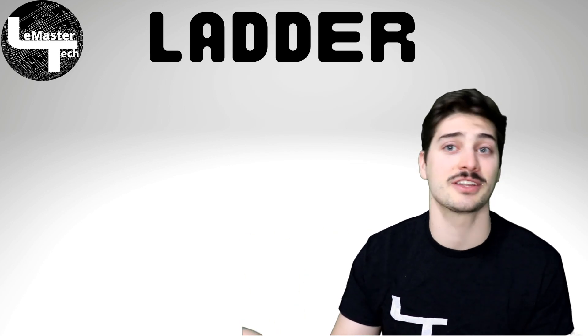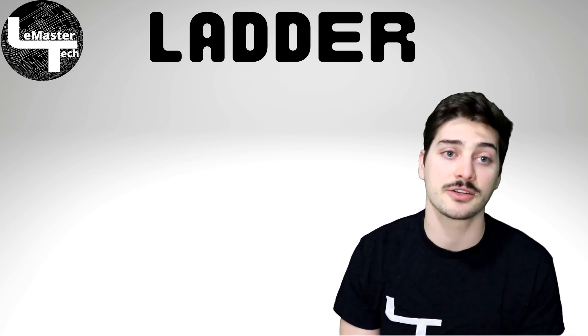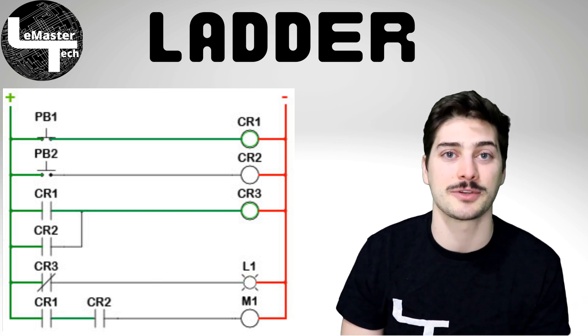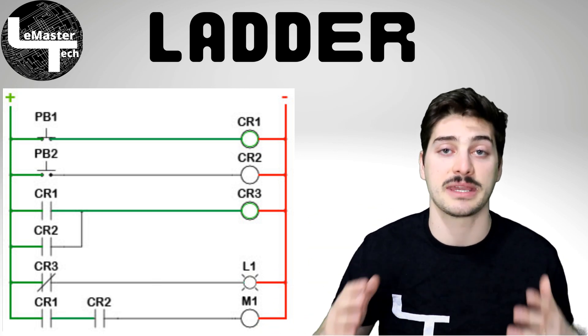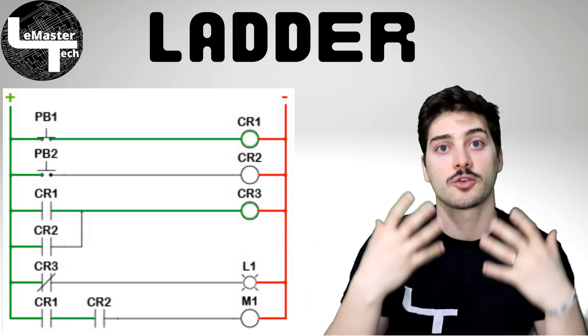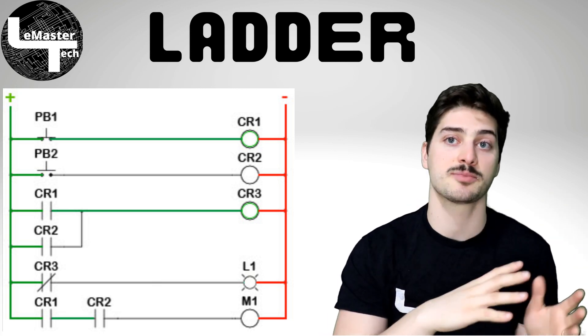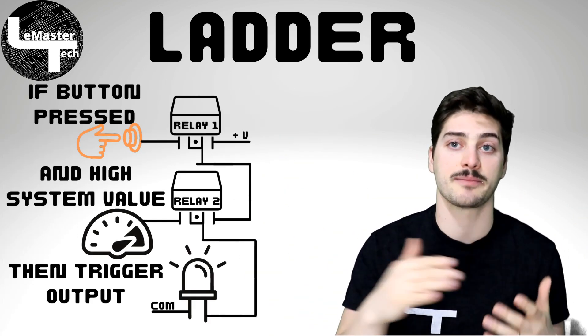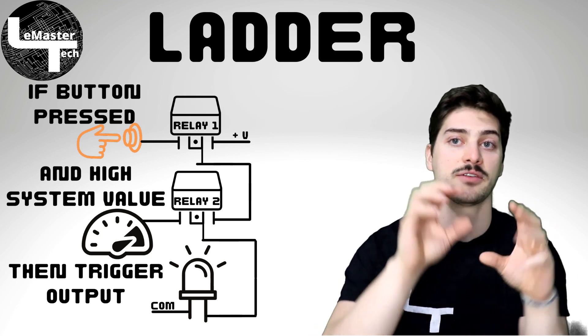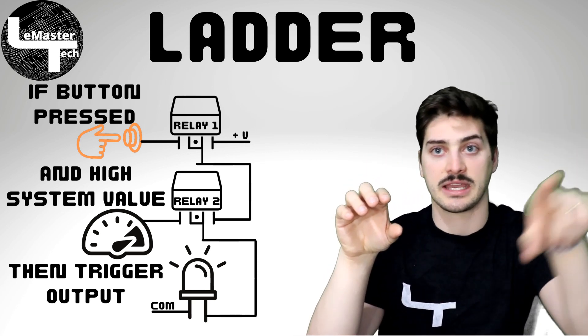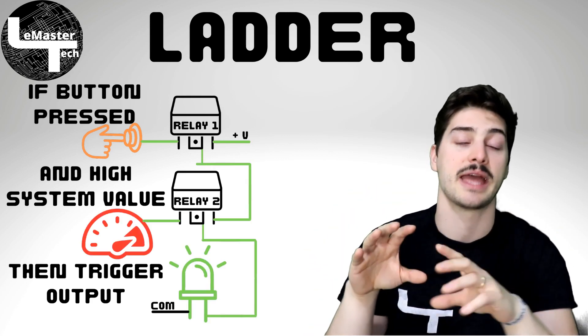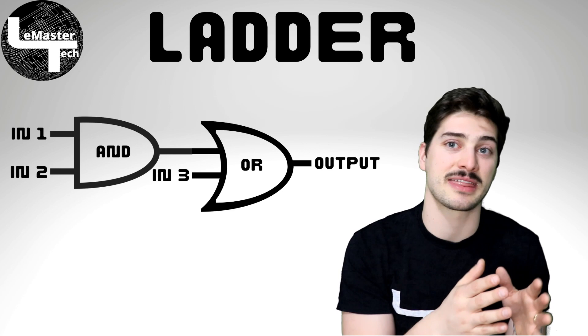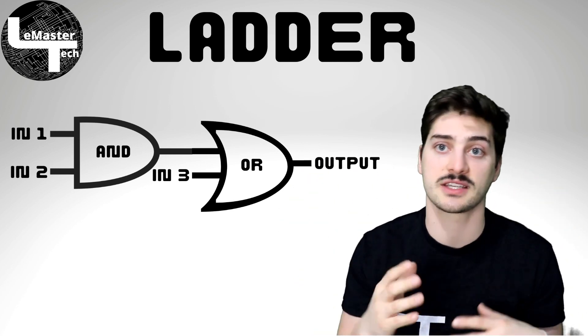Let's start with my personal favorite and potentially the most common one: Ladder Logic. Ladder Diagram, or LD, is essentially the first PLC programming language that came up organically because it looks a lot like electronic relay schematics. In the old days before PLCs, you would read controls maps as schematics of different relays — for example, a relay that checks if a button was pressed and a high-pressure switch was met, and if both were true the relay would pull in. A standard programmer might think of this as a series of AND or OR gates for binary logic.